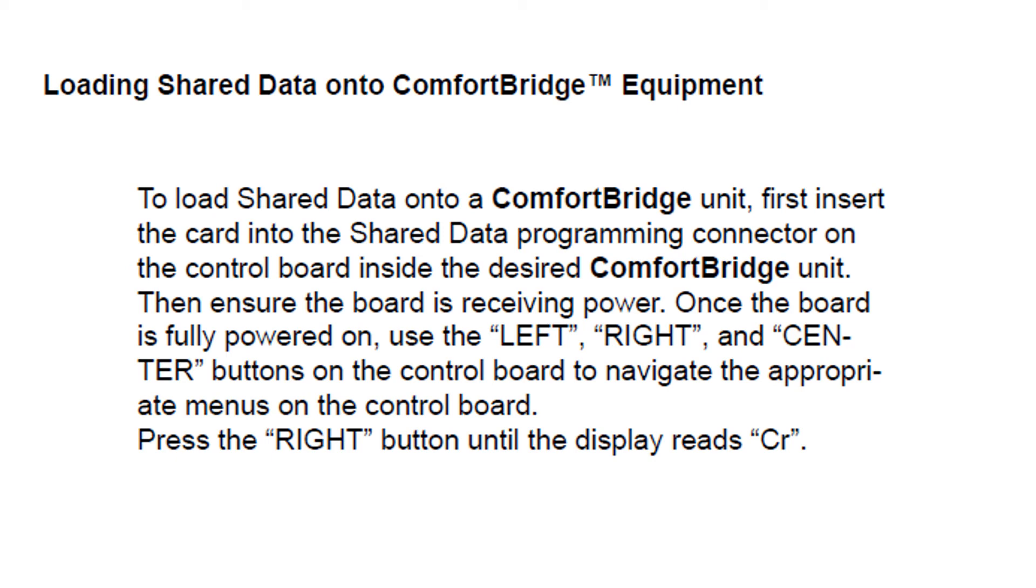To load the shared data on Comfort Bridge equipment, first, with power down, insert the card into the program slot. Turn the power back on. Once the board is fully powered on, use the left, right, and center buttons to navigate. You'll press the right button to see CR on the screen.